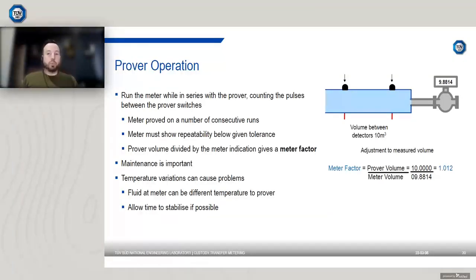Typically, when you prove a meter, it needs to be proved on a number of consecutive runs. The reason for consecutive runs is to show repeatability below a given tolerance. Maintenance of a prover is obviously important because you're relying on the calibrated volume in the prover, and you're relying on things triggering the detector switches. If the prover isn't maintained, it can affect the quality of the prove. Another key consideration is variations in conditions at your flow meter and the prover. If the temperature is different between the meter and the prover, you're going to have different fluid properties, for example thermal expansion. It's always good, if possible, to allow conditions to stabilise, because that leads to a much better prove.